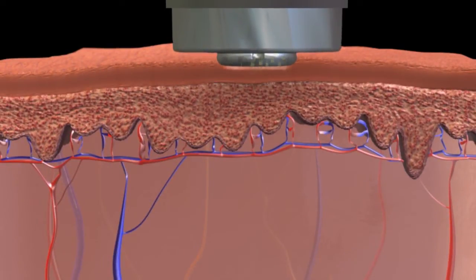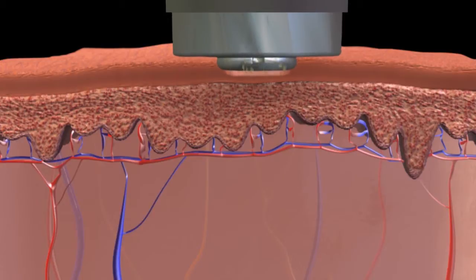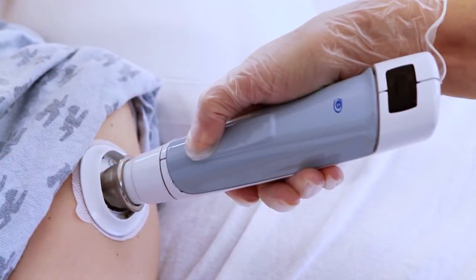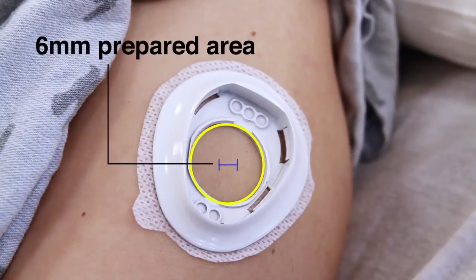Prelude is designed to consistently and precisely remove only the stratum corneum, or dead outer layer of the epidermis, using microdermabrasion. After approximately 10 to 15 seconds, Prelude's patented control algorithm automatically stops at the juncture of the dead tissue and the live tissue. The prepared site is only 6 millimeters in diameter.